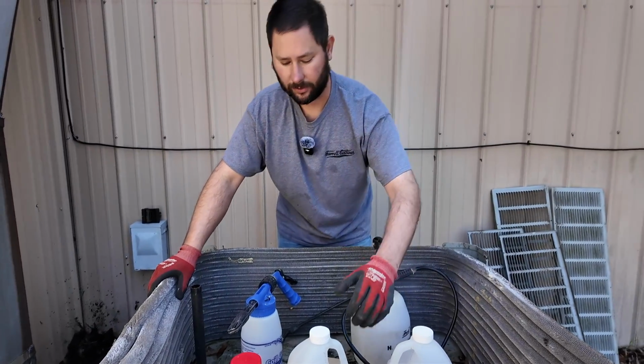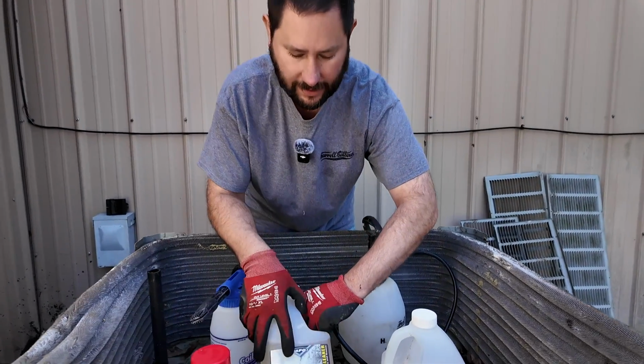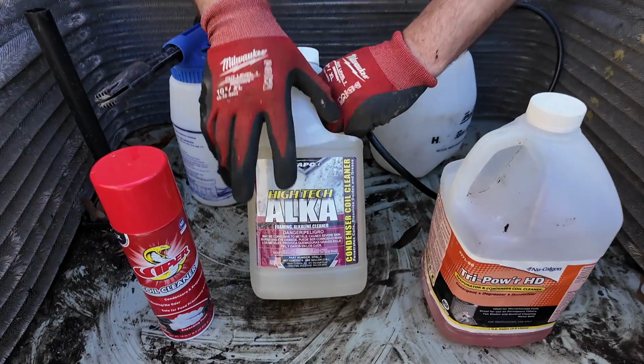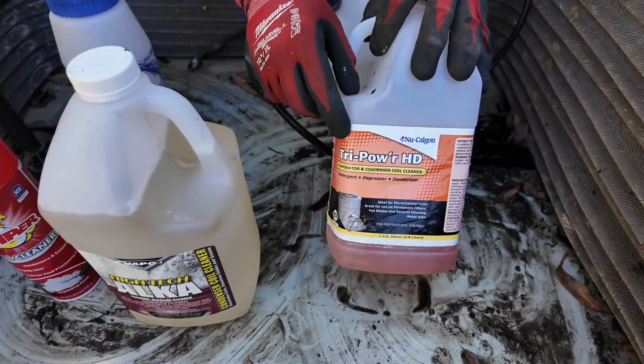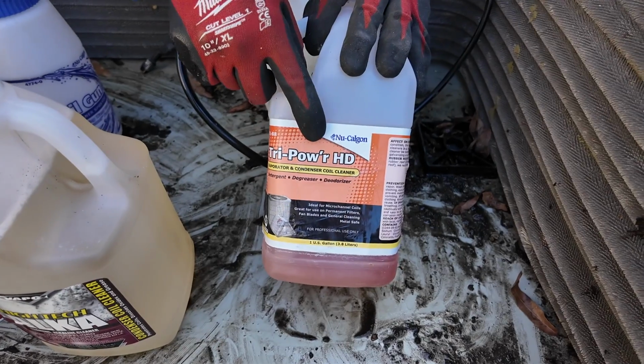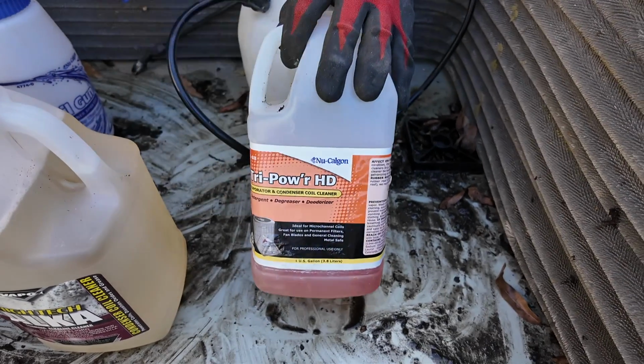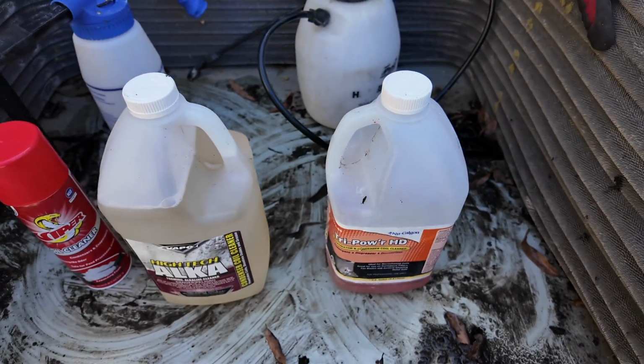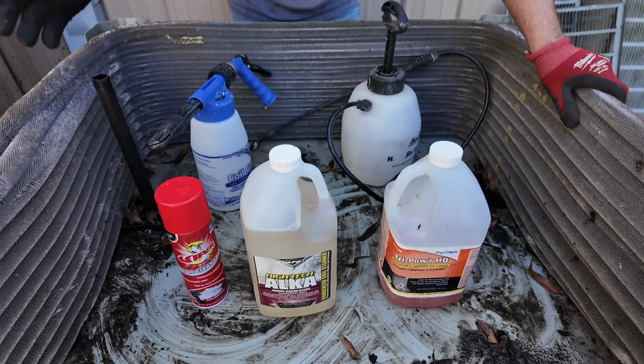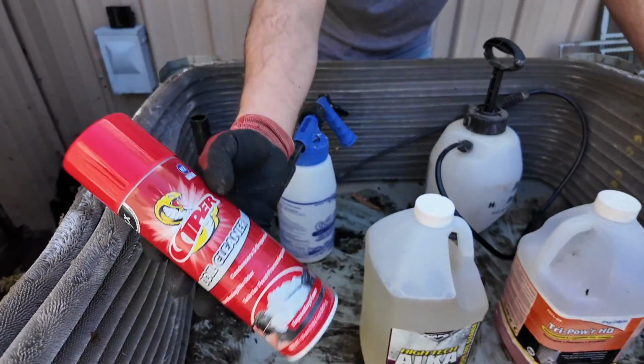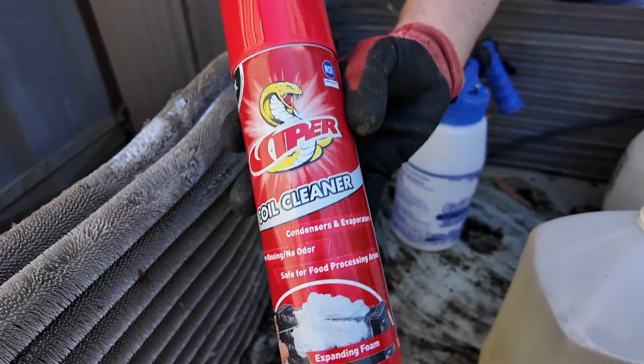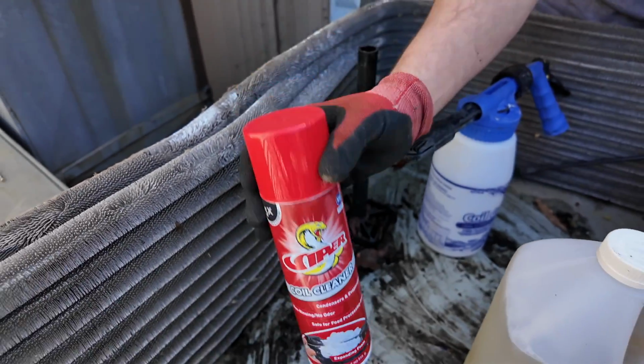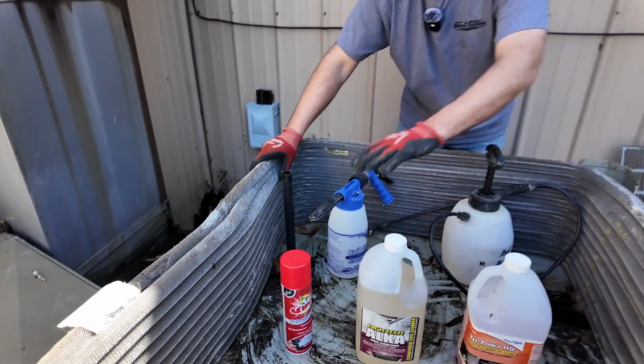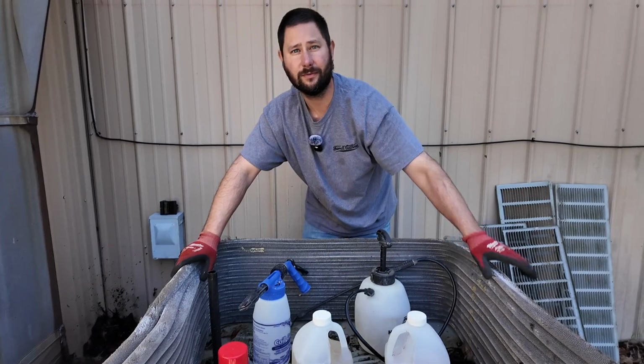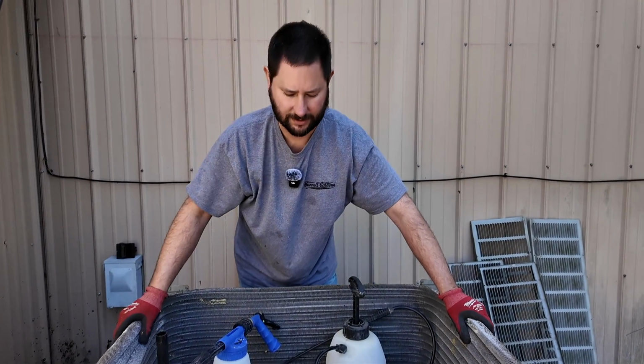Got a couple coil cleaner choices. This right here is Hi-Tech Alka, and this is for condensers, condenser coils. And this right here is Tri-Power. I like this because you can use this for micro-channel coils, or this spine fin coil here, or any aluminum copper coil. Then we've got this Viper coil cleaner. This is what I would use to wash off my evaporators. I don't typically use this for condensers. I use it for indoor coils where you have a split system.